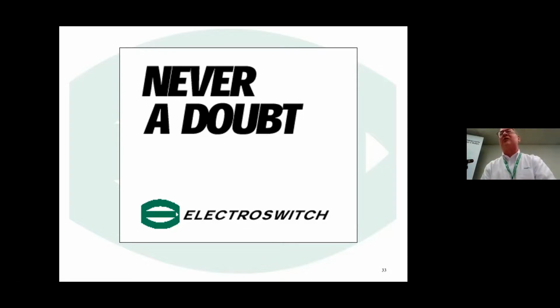You know, in current transformers, you cannot really open circuit a current transformer because you have such magnetic potential already built up on it. If you leave that circuit open, it can cause either damage or failure, or harm someone, because there's a magnetic voltage built up on that current transformer. Hopefully that answers the question, and I do have some visuals that I could send anybody who is looking for more detail on how a slip contact operates.